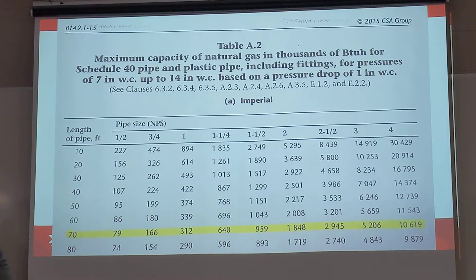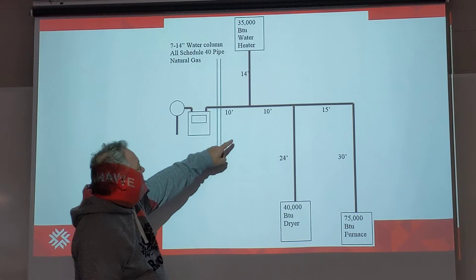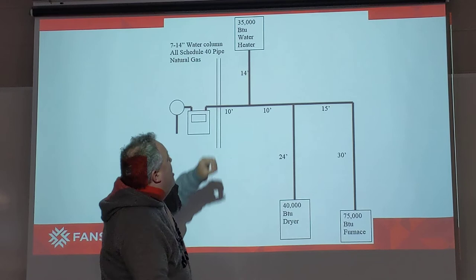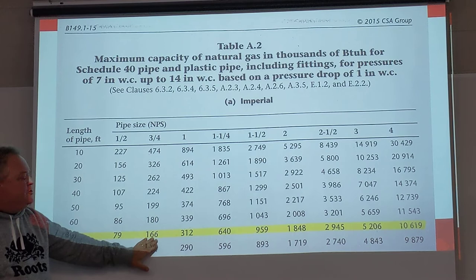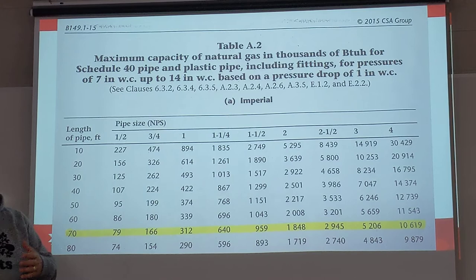The final piece we're going to size is the 10-footer that serves fuel for all of the appliances. We're going to add all the BTUs together — 150,000 BTUs total. At the 70-foot code zone, three-quarter inch will do just fine at 166,000 BTUs. So three-quarter inch is what we would use from the meter coming in on that first pipe.